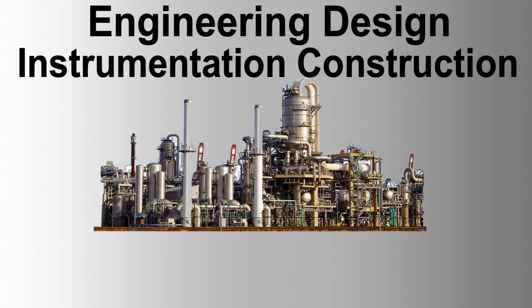Mounting materials containing asbestos and asbestos in non-composite form shall not be used. Mounting materials shall be selected to avoid electrolytic corrosion. All pressure instruments fitted with blowout vents shall be mounted with a clearance equal to at least one blowout vent diameter between the vent and nearest obstructing surface. Modifications to prefabricated panels must not be made without the company's approval. Items such as miniature control valves, solenoid valves, etc., for mounting behind panels, and whose position is not previously specified, shall be rack-mounted on an approved framework.